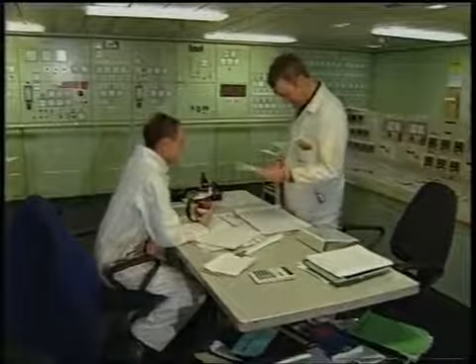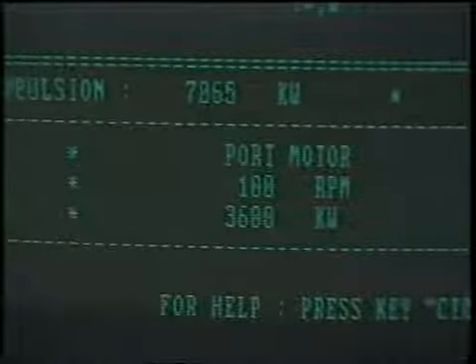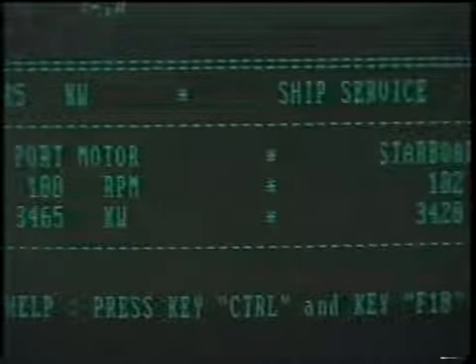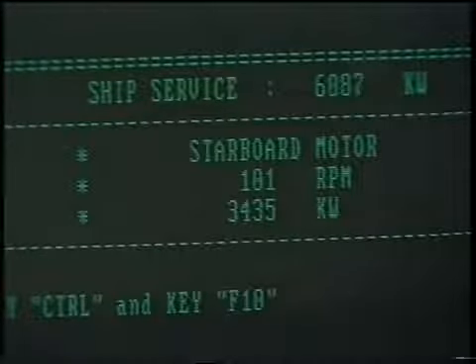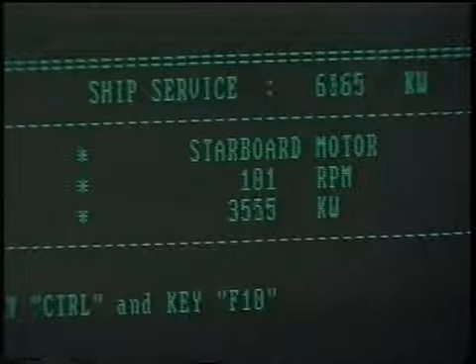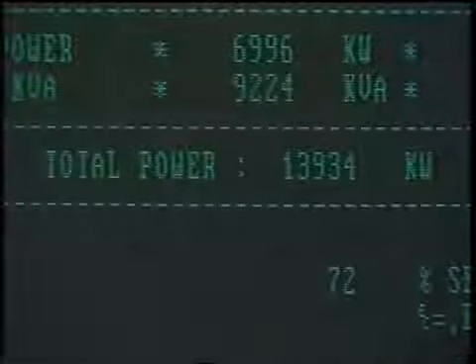With so many varying demands on the power supply, it is essential to have a power management system, PMS, to control its distribution and to run the power system efficiently and safely. There are situations, for instance, where it is permissible to limit propulsion load to maintain full power to the hotel services. Typically, the system sequences the generators evenly and runs individual generators at a high load factor for maximum fuel economy. It is a totally automated system which can be overridden by the chief engineer.